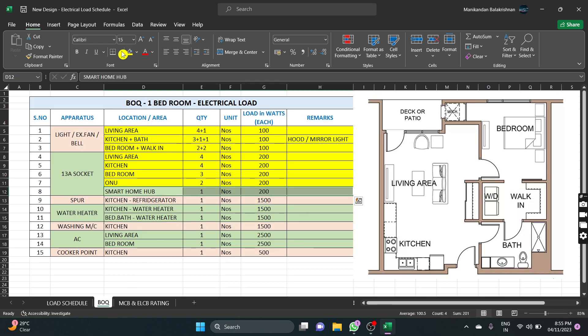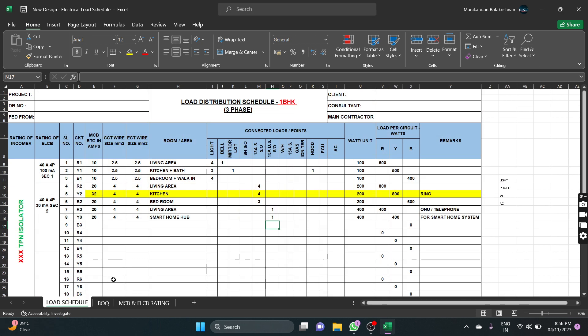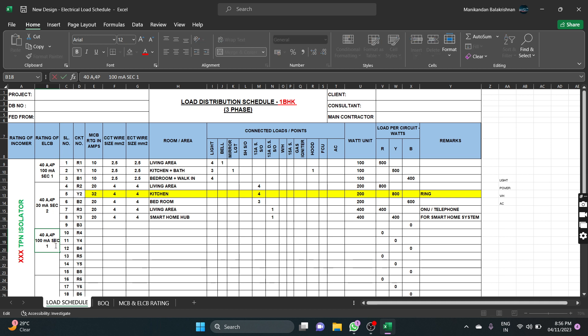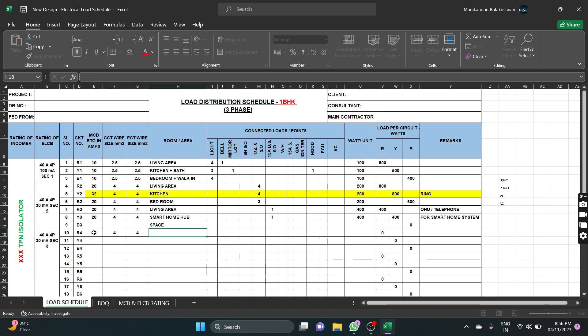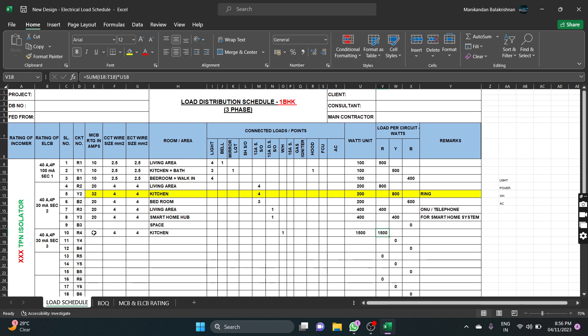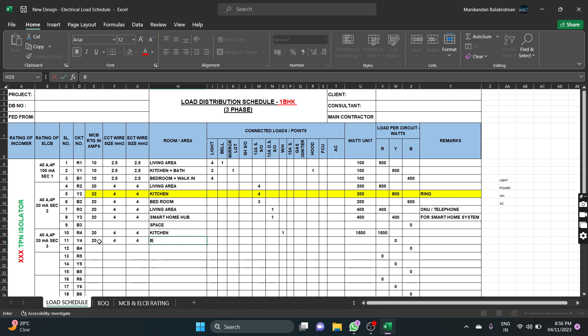Now we get to the kitchen: one outlet with DB switch for the refrigerator, kitchen water heater. Bedroom water heater is on a separate section — section number 3. Water heater ELCB is 30mA. Kitchen water heater is 1500W, and bathroom water heater is also 1500W.